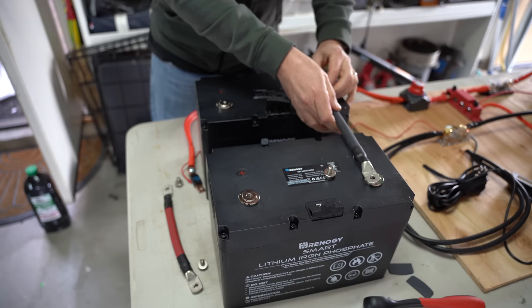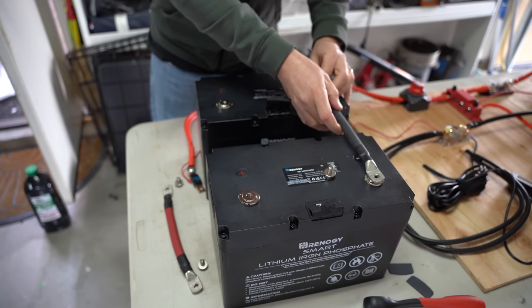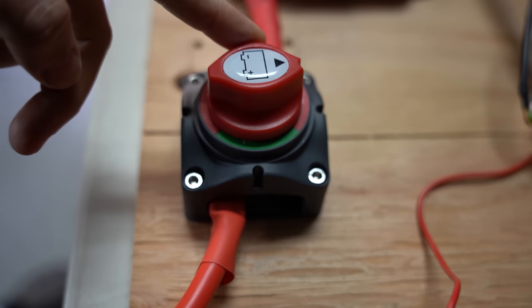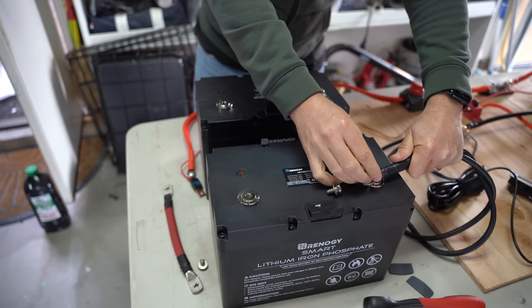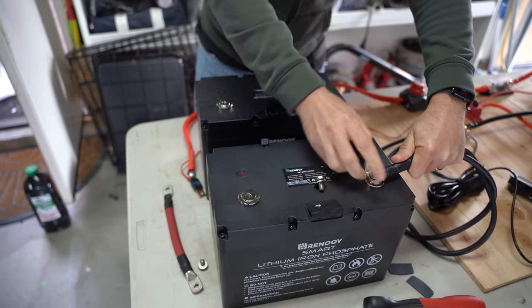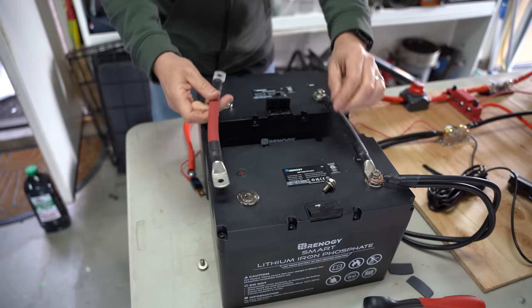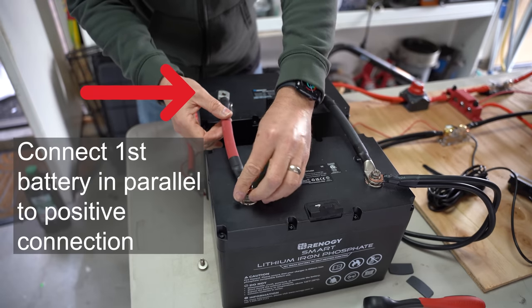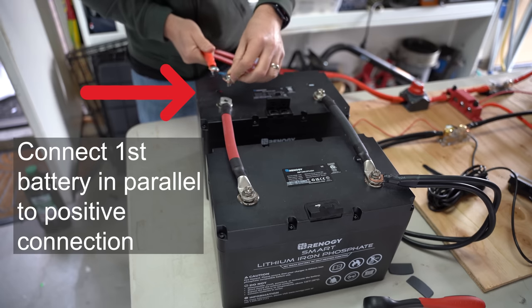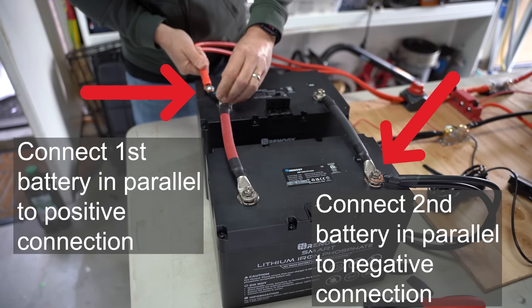or we can monitor them with a battery monitor that we installed earlier when connecting to the shunt. To connect the batteries to our system, first make sure the switch we installed is in the off position. Since we have two batteries in parallel, I'll connect the positive cable coming from our system to the positive terminal on the first battery, and the negative cable on the negative terminal on the second battery.